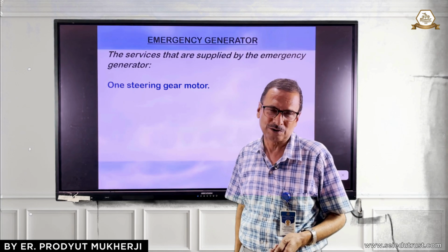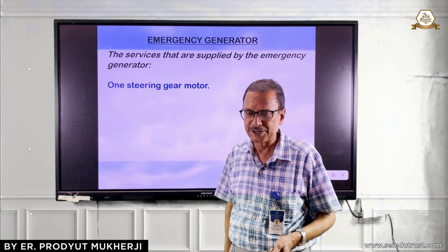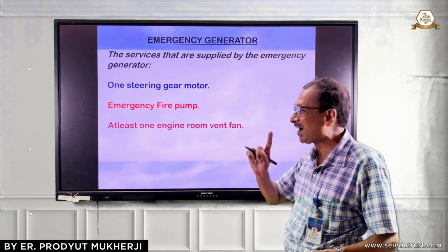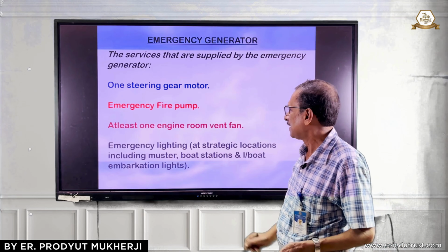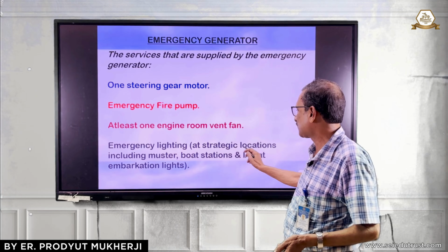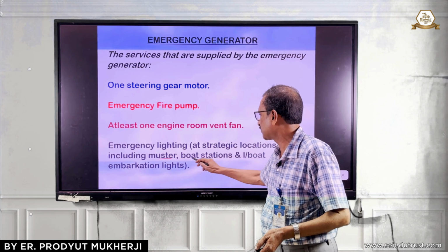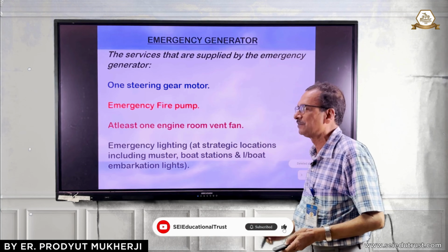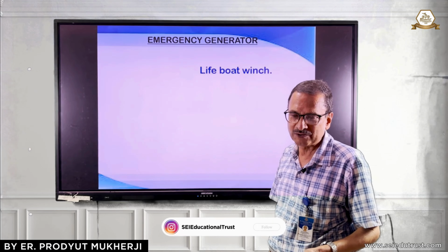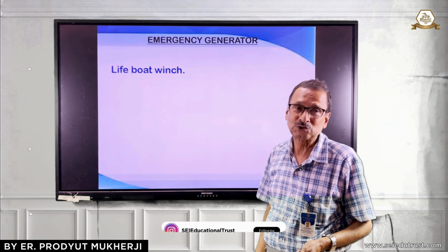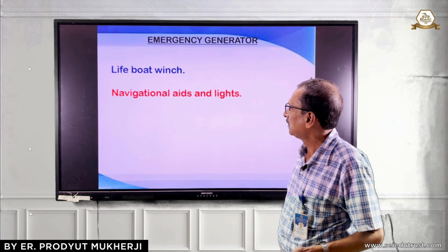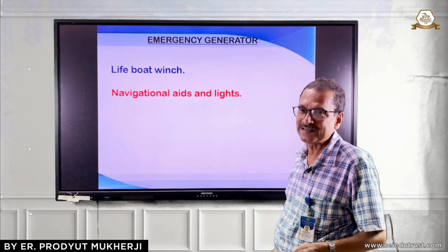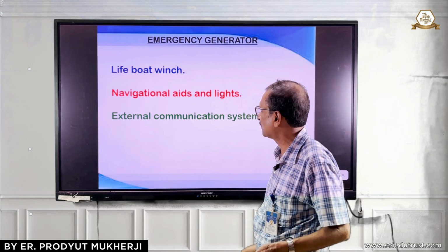One steering gear motor, both is not required. One steering gear motor, emergency fire pump, at least one engine room vent fan, emergency lighting, strategic locations including the muster station, boat station and lifeboat embarkation lights. Yes, there are more emergency equipment, lifeboat winch to hoist the lifeboat, navigational aids and lights, GPS, LRIT, all these, and the navigation lights.